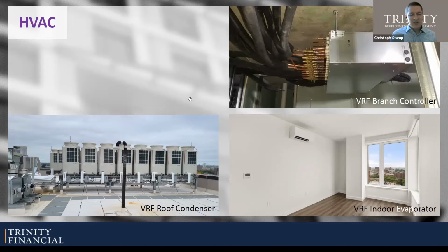We have an energy recovery VRF system, and the top right is a box that enables that. One condenser, as I mentioned, serves an entire floor. So with this system, you can heat in one apartment and cool in the other apartment on the same floor in the same system. It turns into a quote unquote three pipe system that enables that, as it's very important to be able to heat and cool at the same time. And this is the magic box to do that. I can't really explain how this works. This is a magic box, that's how I call it. So those are really the main differences.